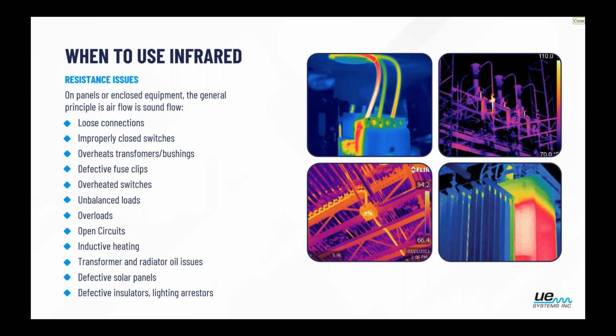This is a perfect example of where ultrasound would not be able to inspect for, but infrared would instantly pick it up, is an unbalanced load coming to the plant. Now, there are always going to be tells within the facility itself if that's an issue, but infrared would always be the first option to check your lines coming in, see if you have unbalanced loads. Overload equipment, open circuits, inductive heating on other pieces of equipment.